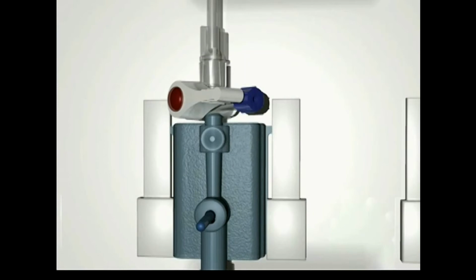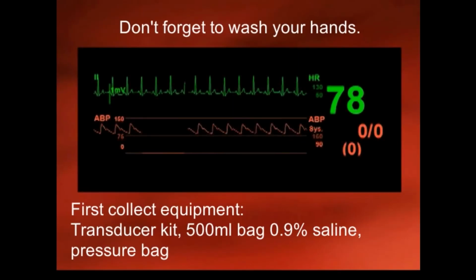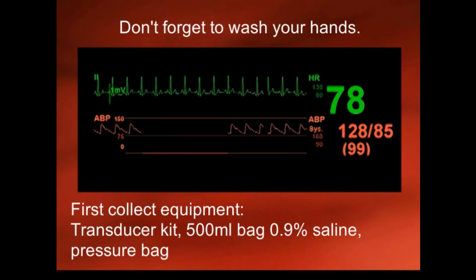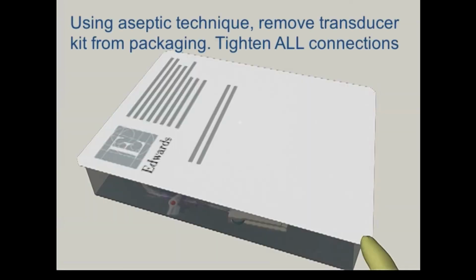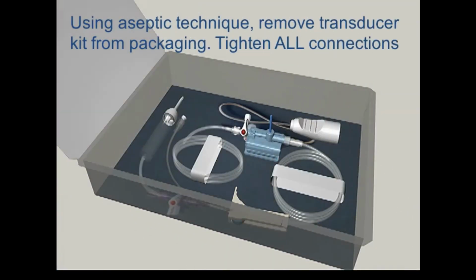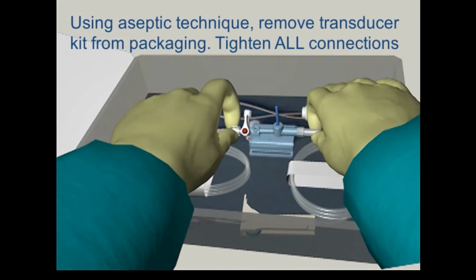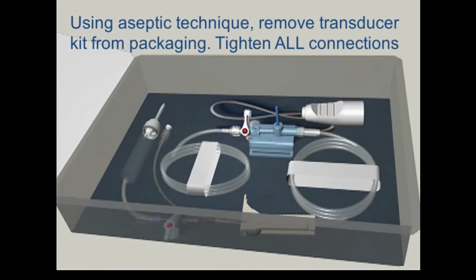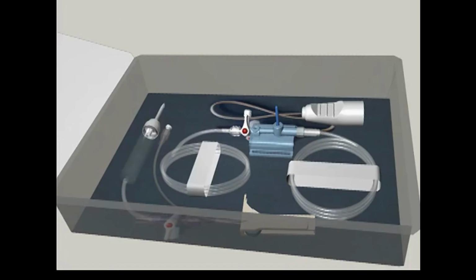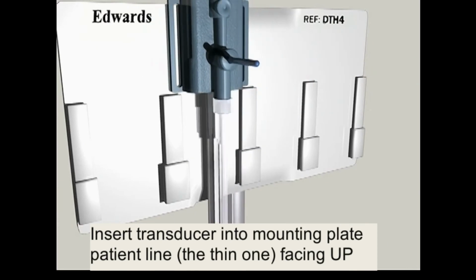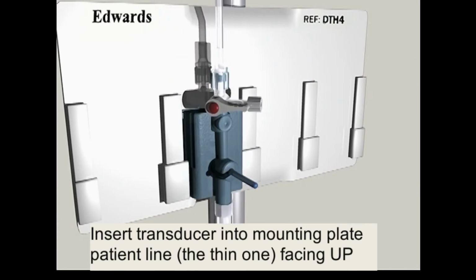The following animation demonstrates best practice in the setup of the TruWave disposable pressure transducer. Prepare the TruWave transducer using the following 6 steps. Step 1. Using aseptic technique, remove the transducer kit from the sterile packaging and ensure all connections are secure. Step 2. Insert the TruWave transducer into a mounting backplate that is secured on an IV pole.